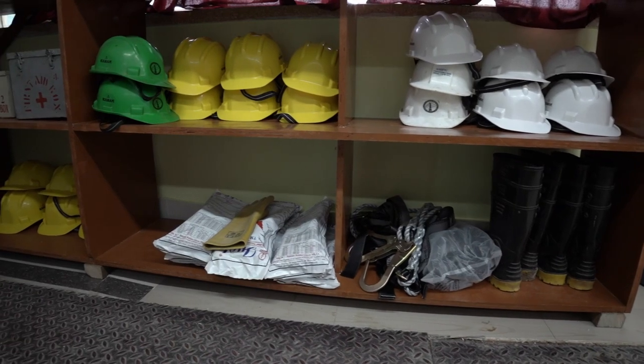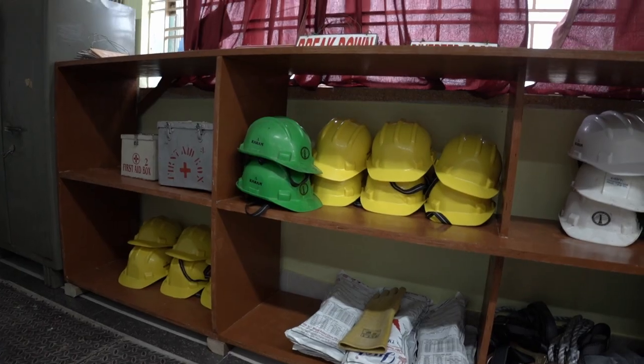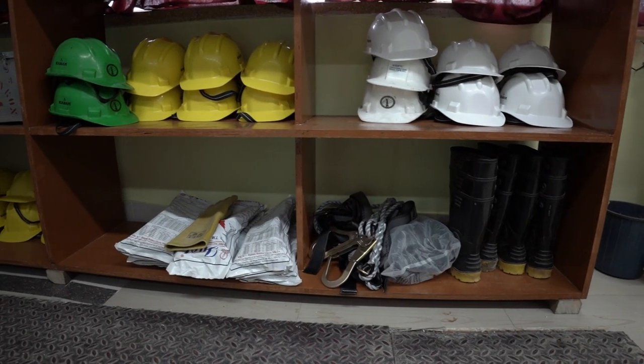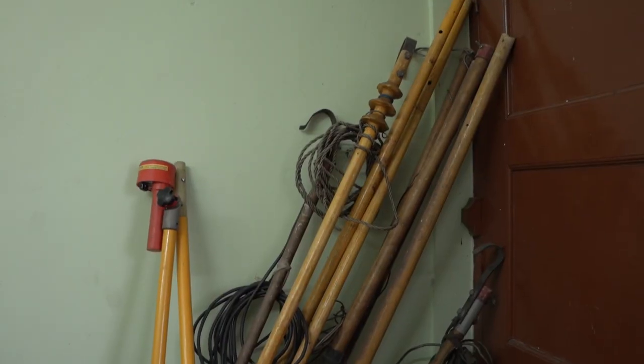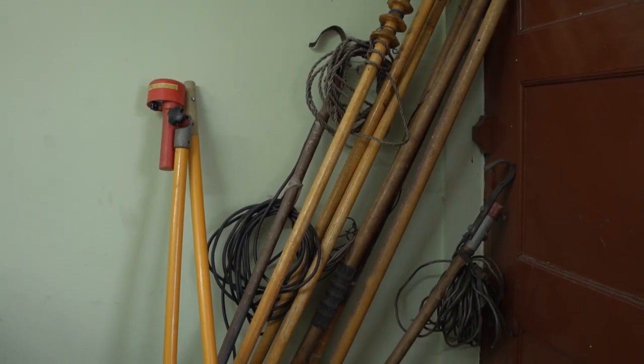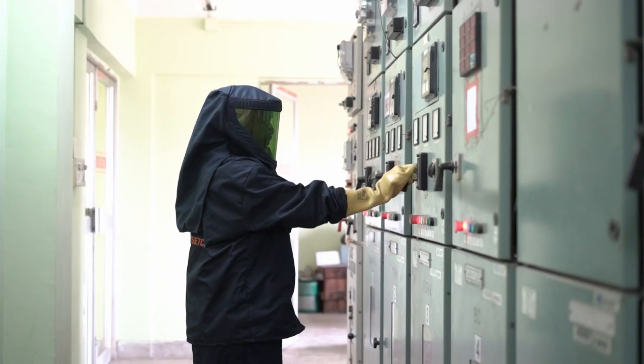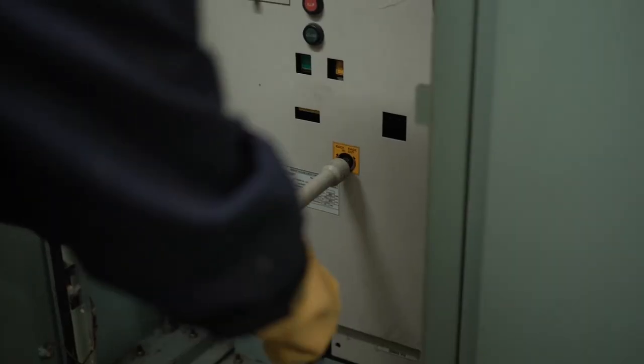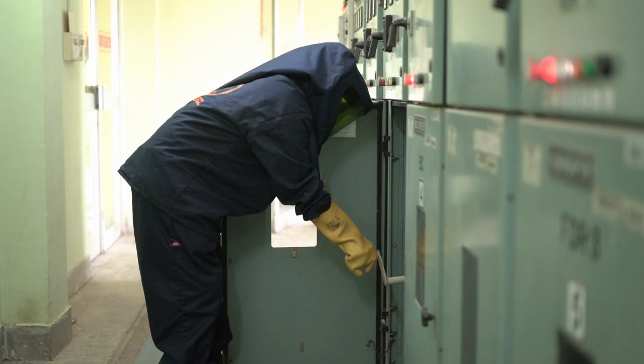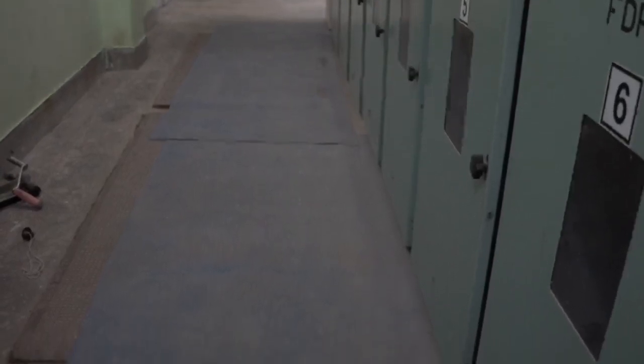PPE and various safety equipment like safety helmet, safety gloves, safety shoe, gumboot, searchlight, first aid box, discharge rod, high voltage detector, safety belt etc. are readily available at the control room and maintenance room. Arc flash protection suit is used during every rack-in and rack-out operation of indoor VCB, and high-quality insulating rubber mat is placed inside the 11kV switchgear room.